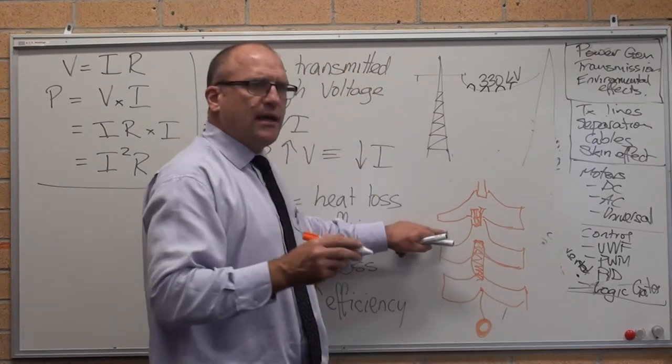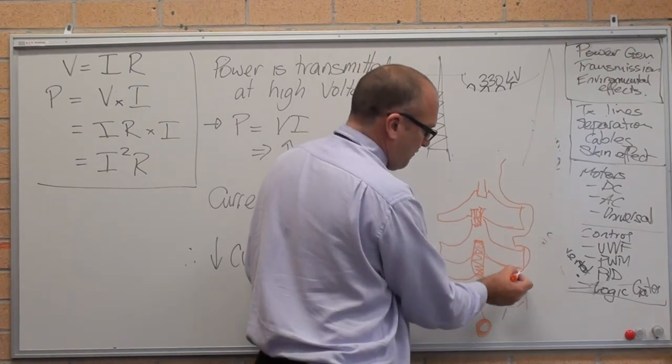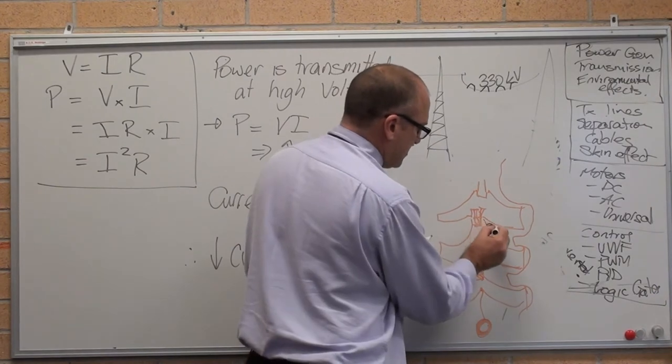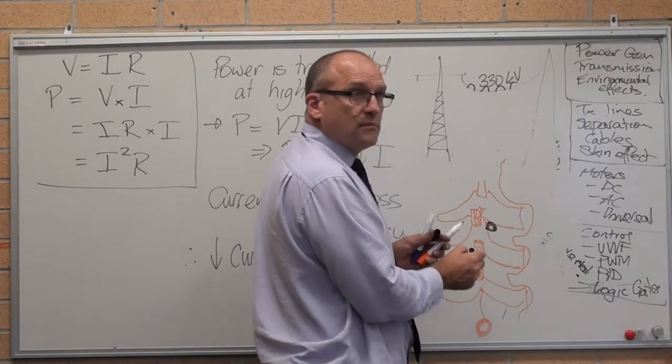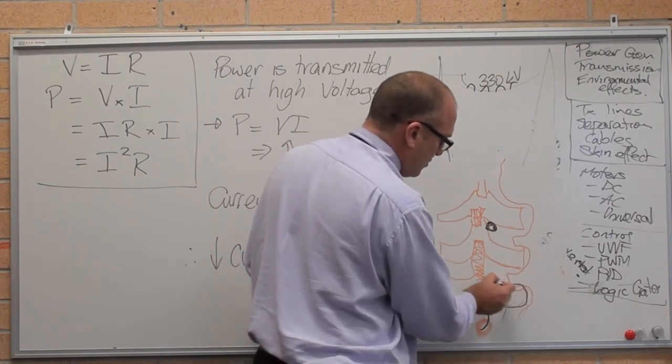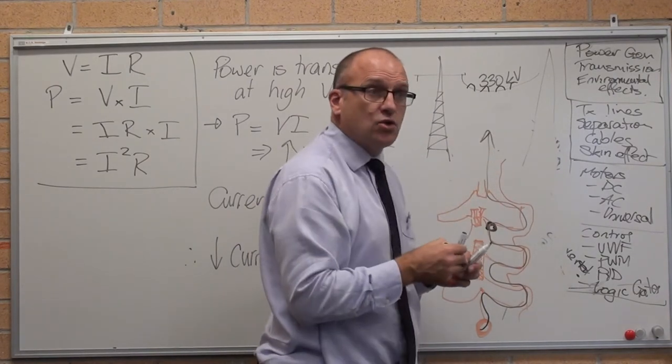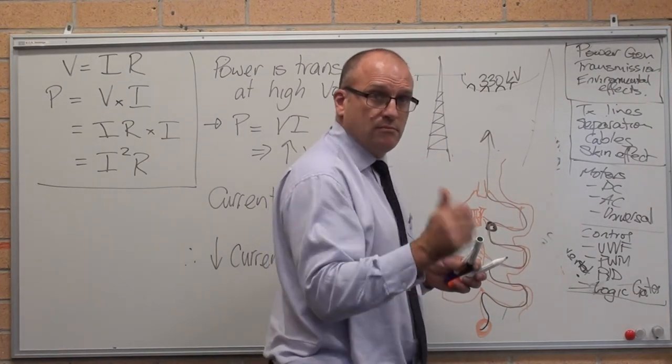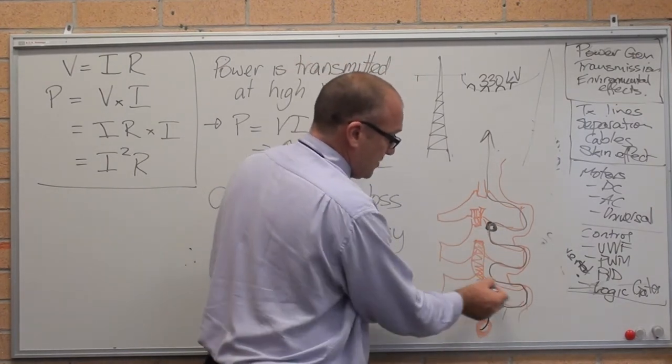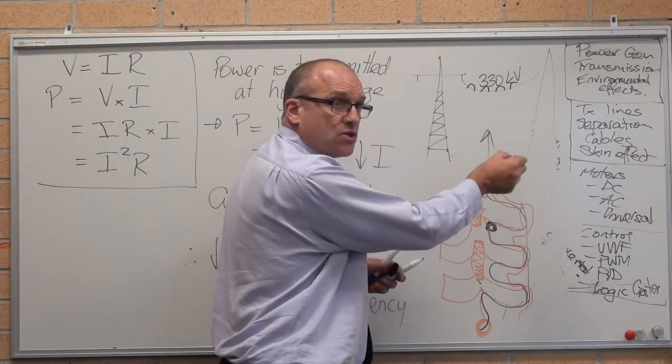They look like that, like little roofs. So when they get wet, the water flows down there and inside here stays dry. Because that stays dry, there's no path for the electricity to travel up and out and short out on the power line. Make sense? As well as, now it's not a straight path. It's got a lot longer path to follow as well if it does short out.